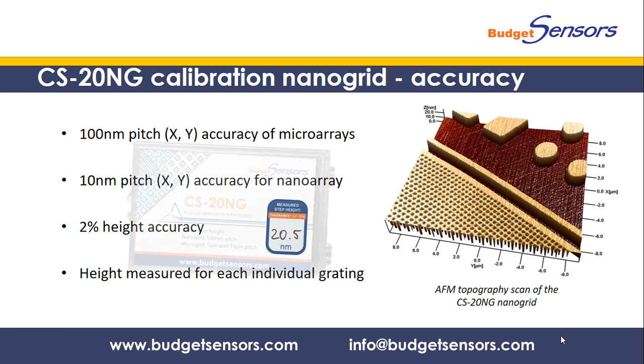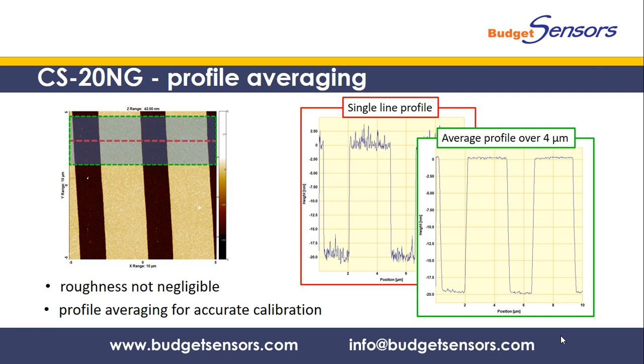Please note that the roughness of the nanogrid surface is not negligible as a percentage of the total step height. Calibrating your AFM system based on a single profile line can lead to a large error. We recommend that a profile is averaged over several micrometers for accurate calibration.